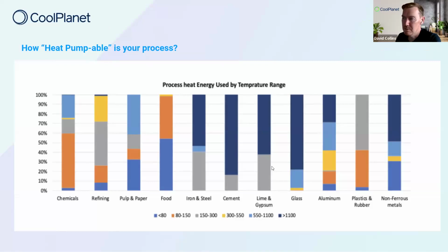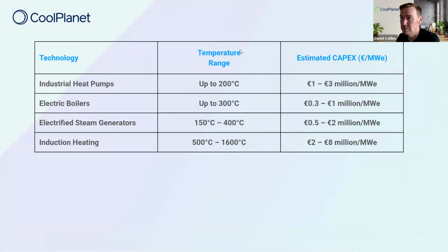Talking a bit about heat pumps, we mentioned temperature. This chart, taken from the internet, looks at different industries from chemicals to food to glass, outlining the temperature requirements — how much of your process demand, for example in food, can get away with 80-degree heat, which could be between 50 to 60%. The balance is at a higher temperature, which will generally be steam. That's what you need to look at when doing your heat mass balance for your site, because a certain type of heat pump may only offset a certain amount of your fossil fuel demand.